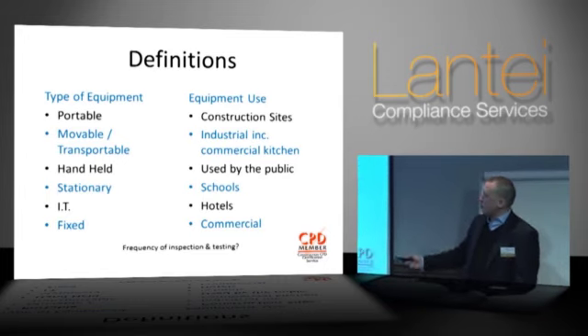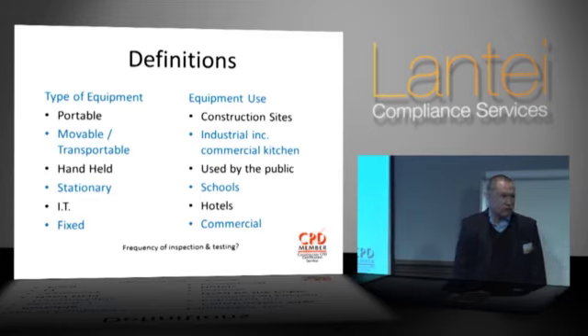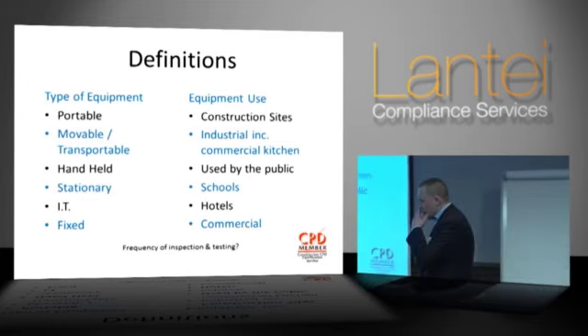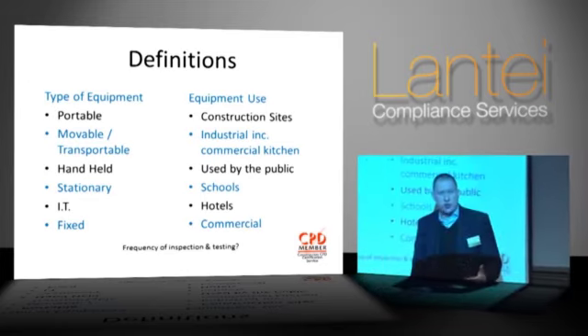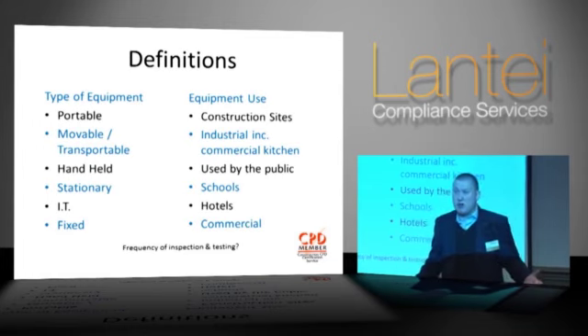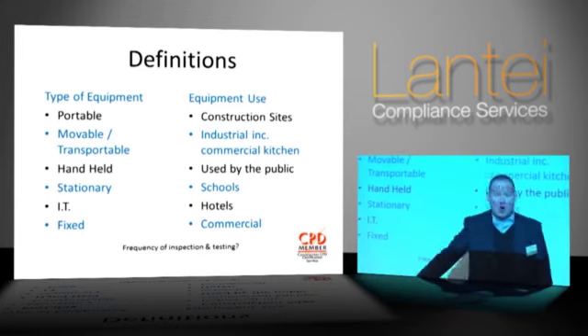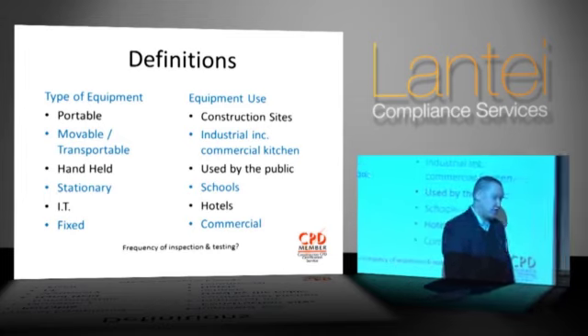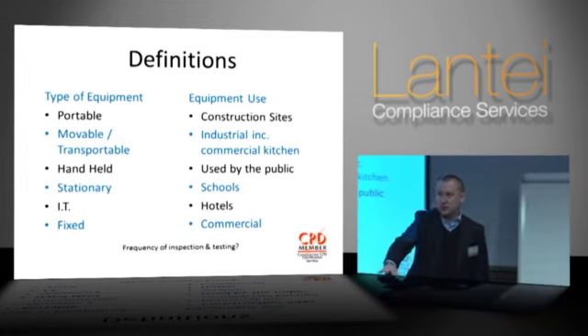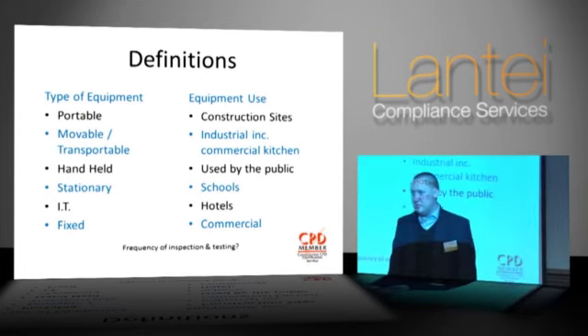Then we also look at what it's used for. A lot of sites or clients we speak to are doing PAT testing on everything every year. But look at something like IT equipment - a PC tower under a desk, put there four years ago. The desk's never been moved, the cable and flex to the socket are all behind that desk. What's the risk of damage to that equipment? It's minimal, isn't it? So why would we need to test and inspect it every year? We don't - or it's highly unlikely that we do.